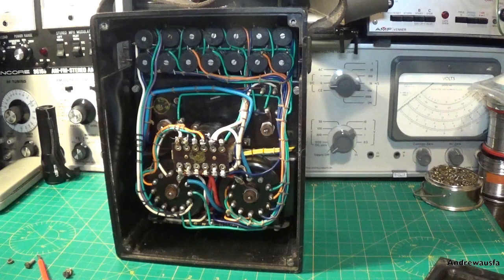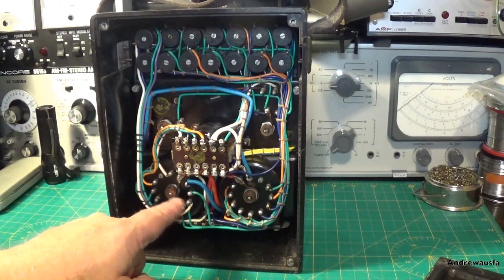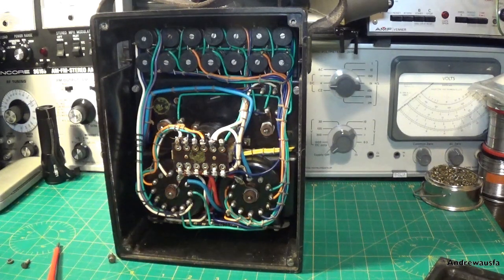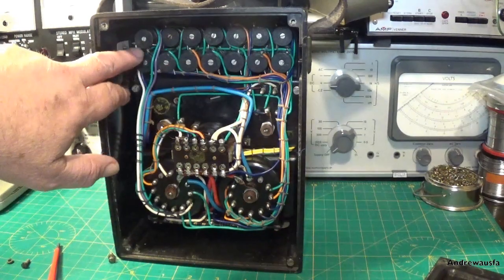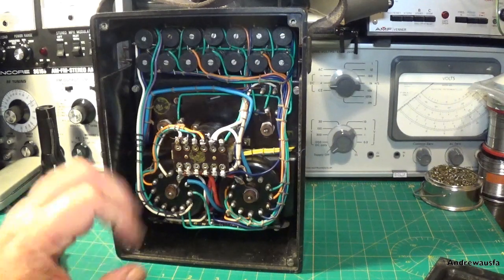So there is the inside of the meter. You have got all the bobbins up the top here, you have got a transformer here. These must be some sort of contact things. The whole movement comes out, and you have got the current shunt board down the bottom here. All these little bobbins will contain very fine litz wire of specific resistances, so the meter needle will rest at what voltage you apply. That sort of thing often goes open because of its age.